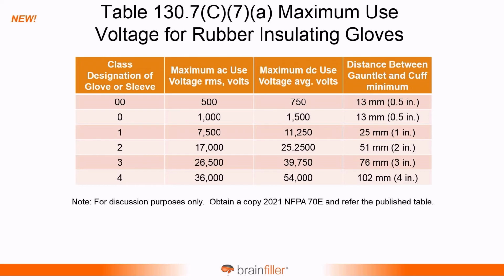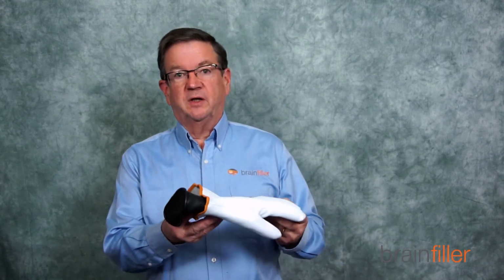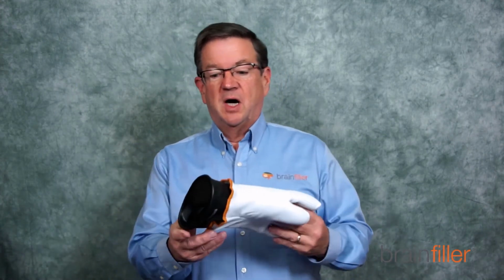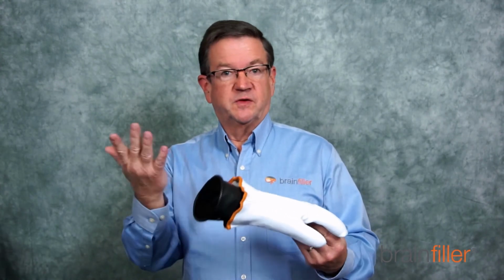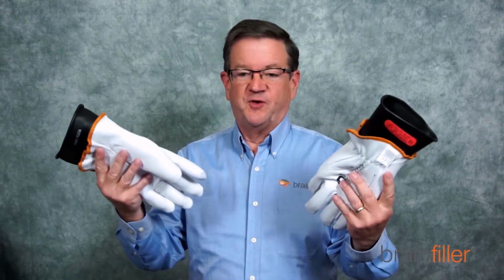And what that table looks like, and notice my note down at the bottom, this is just for discussion. You actually need to use the actual table from NFPA 70E when that comes out. But this shows the different classes of gloves and the voltage ratings. And on the right, the minimum distance between the gauntlet and the cuff. So when you have your voltage rated glove and your leather protector, right in here, there's a certain minimum distance that's required. Usually you far exceed it, but there is a certain minimum distance for that.